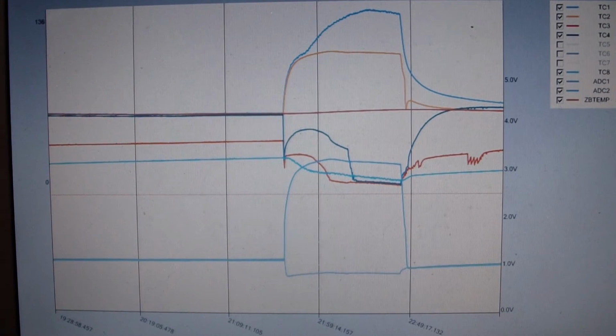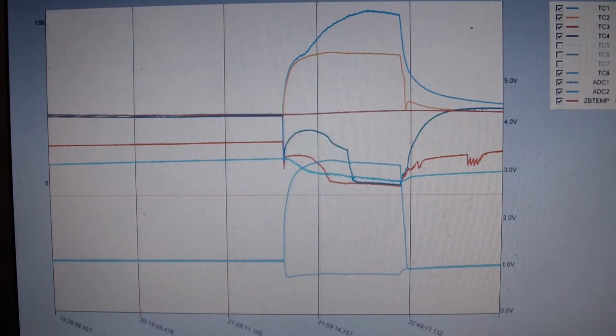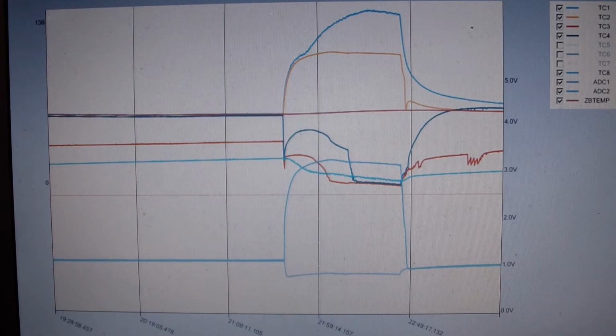So I want to talk about some of my observations and some of my plans here for the near future. What you're looking at here is about 5 hours or so of data. Most of the run times here that you can see are pretty similar, so I just picked this one because it's a pretty commonly looking one. Run times usually somewhere about an hour and a half run time, and then off time is usually somewhere between about 4 to 9 hours, depending on ambient conditions. The warmer it is, the shorter the off time.